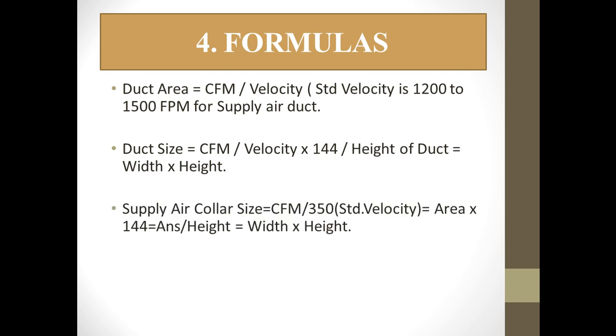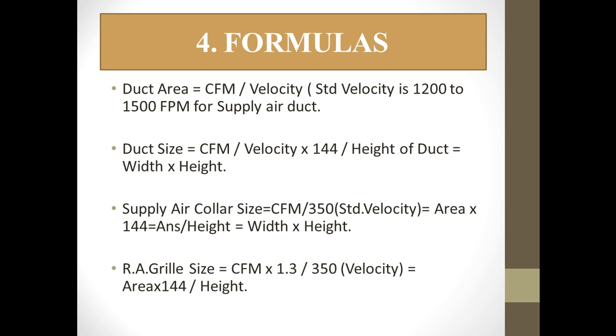To calculate the supply collar size: Supply Collar Size = CFM / 350, where 350 is the standard velocity required for supply air collar sizing. Multiply the resulting area by 144 to convert to square inches, then divide by the collar height to get the width. This gives you width × height — the supply air collar size.